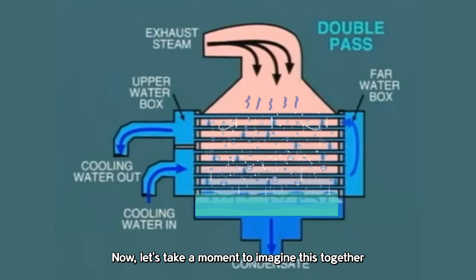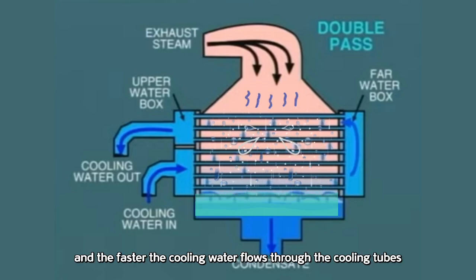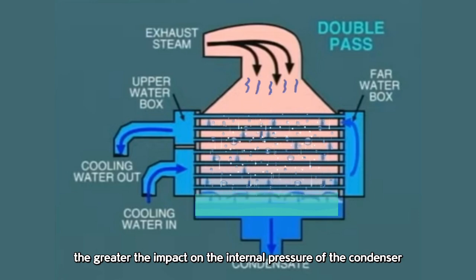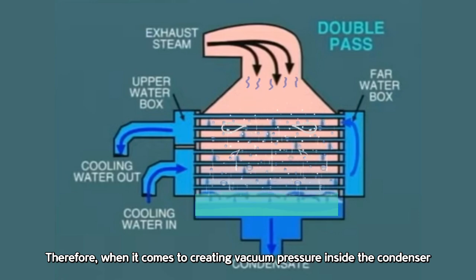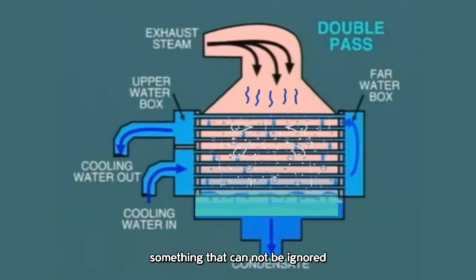Now let's take a moment to imagine this together. The lower the cooling water temperature, and the faster the cooling water flows through the cooling tubes, the greater the impact on the internal pressure of the condenser. Therefore, when it comes to creating vacuum pressure inside the condenser, the temperature of the cooling water is something that cannot be ignored.